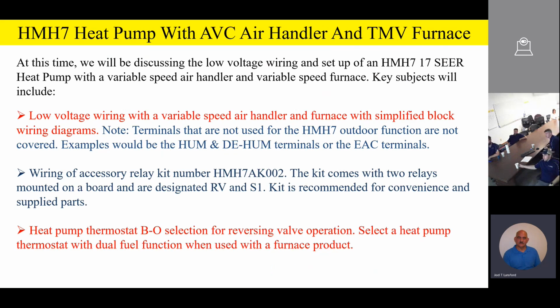All right, so team, at this time, we're going to take a look at some variable speed air handler and a variable speed furnace. And just like we did before, we're going to have a low voltage wiring block diagram. We're going to look at those block diagrams. Now, it should be noted, some of the terminals that we're not going to be using for the HMH7 outdoor unit are not covered. For an example, we're not going to talk about the humidifier terminal, or the dehumidifier terminal, or the electronic air cleaner terminals, because that doesn't have any function.